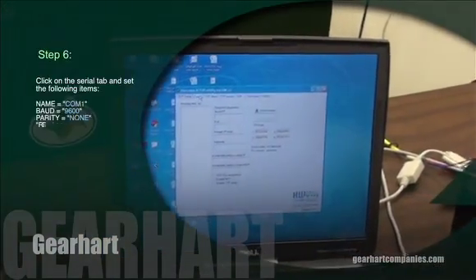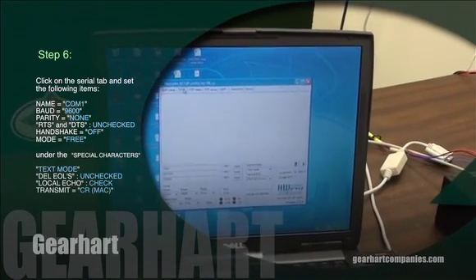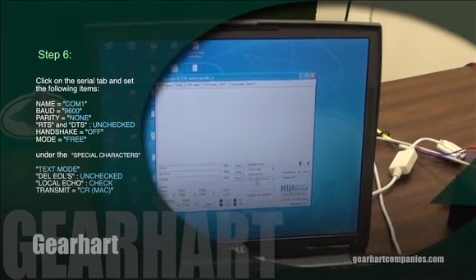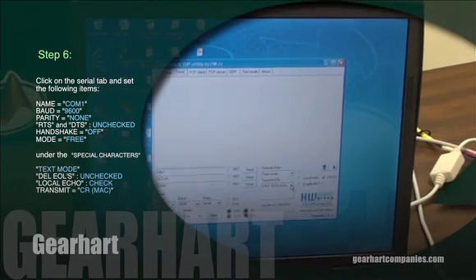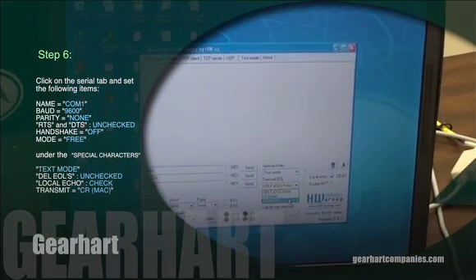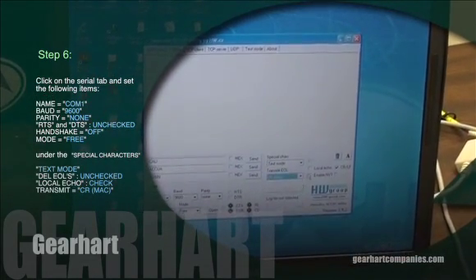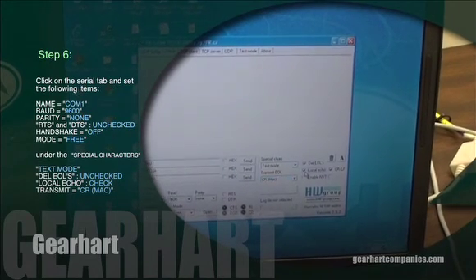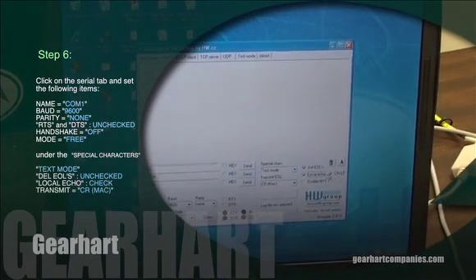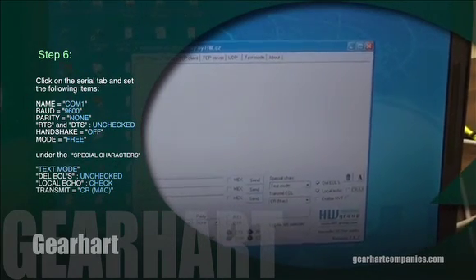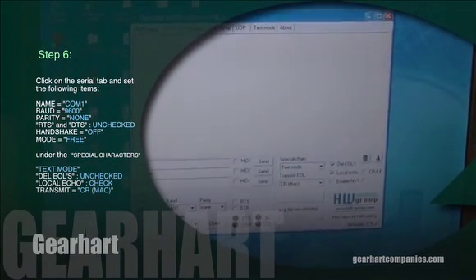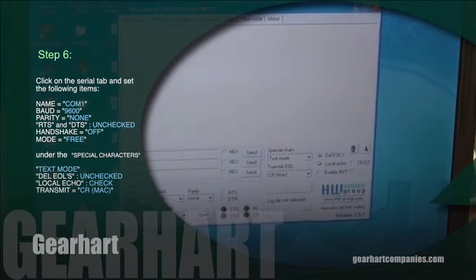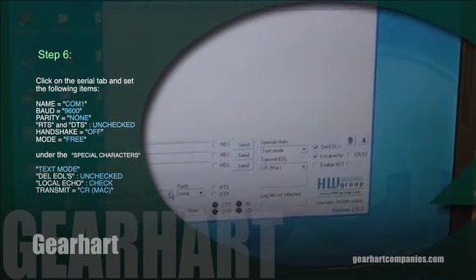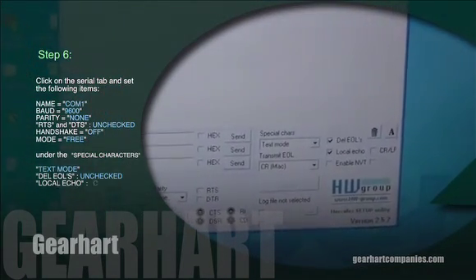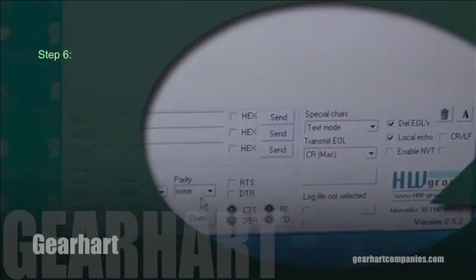Step 6. Click on the Serial tab and set the following items. Name to COM1, this will not always be correct, you may have to find it. BAUD to 9600, parity to none, RTS and DTR unchecked, handshake to off, mode to free. Under the Special Characters tab, select Text Mode, DEL, EOLs to unchecked, Local Echo checked, and Transmit to CR (Mac).